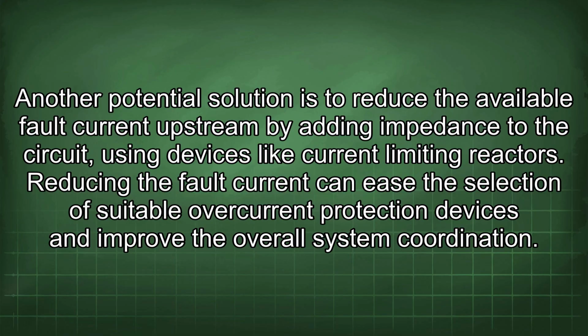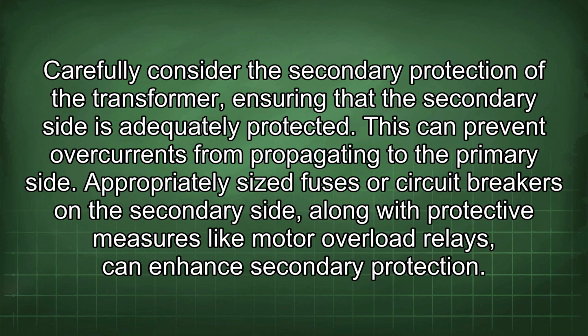Another potential solution is to reduce the available fault current upstream by adding impedance to the circuit, using devices like current limiting reactors. Reducing the fault current can ease the selection of suitable overcurrent protection devices and improve the overall system coordination. Carefully consider the secondary protection of the transformer, ensuring that the secondary side is adequately protected. This can prevent overcurrents from propagating to the primary side.